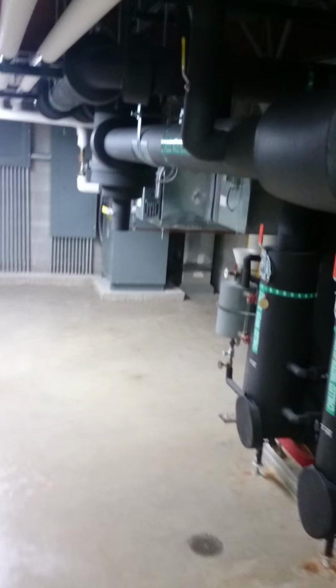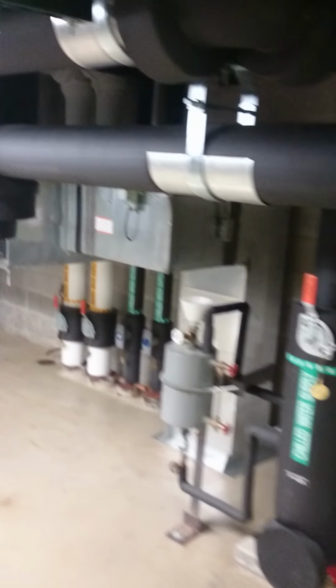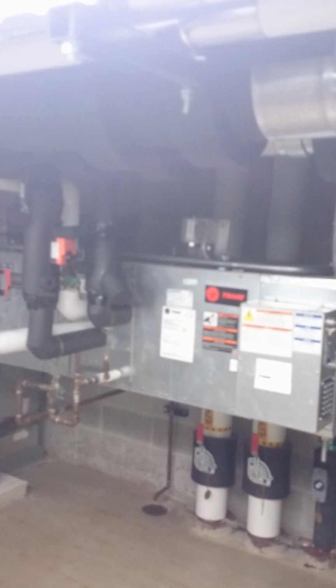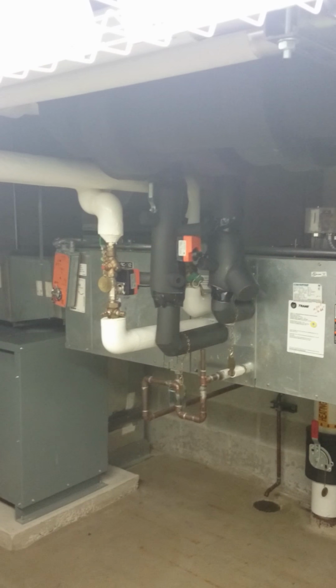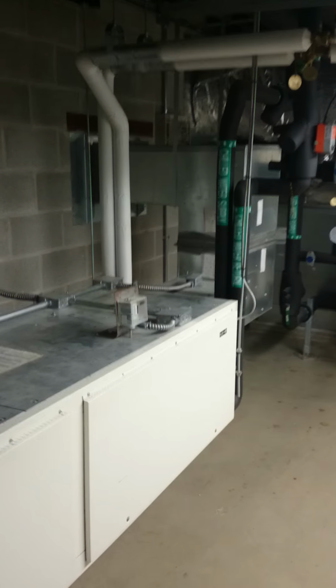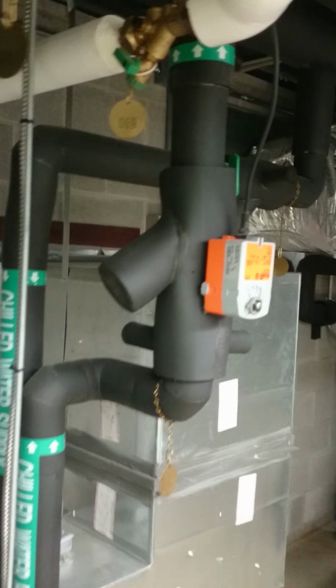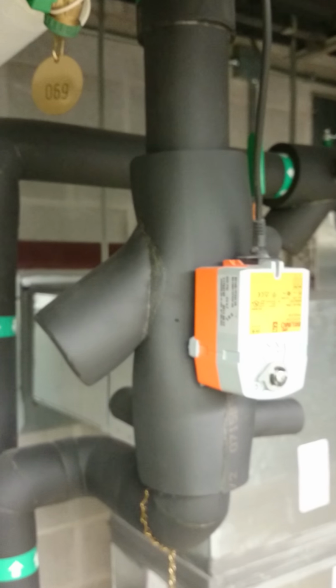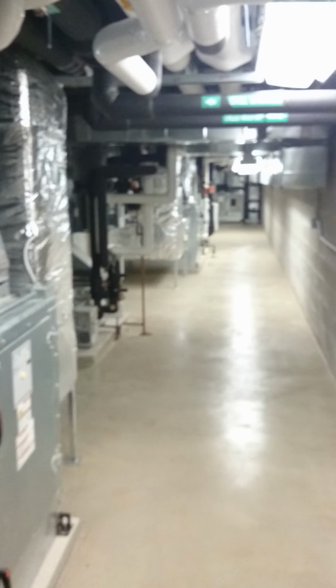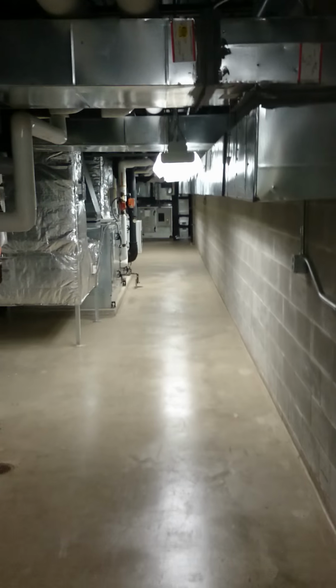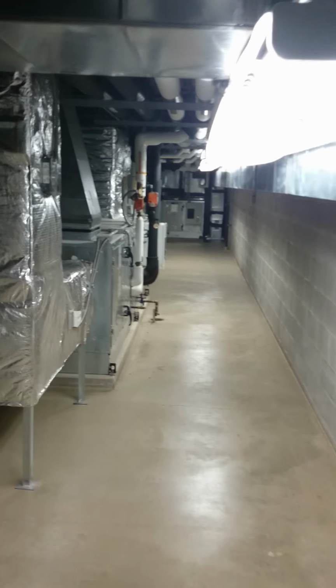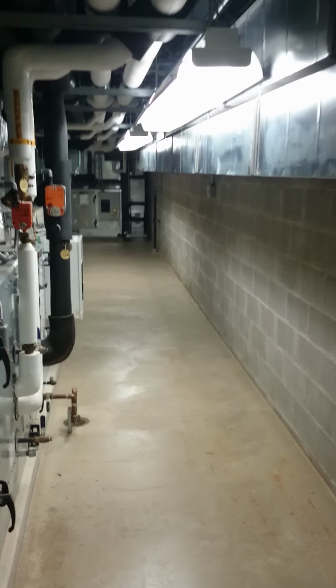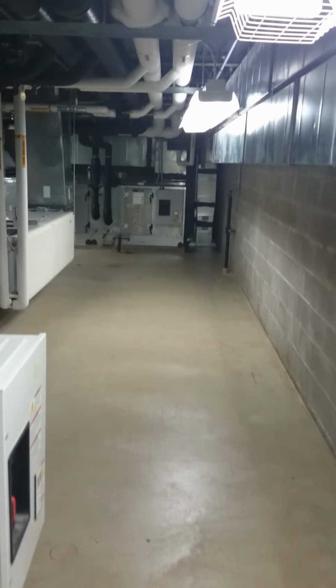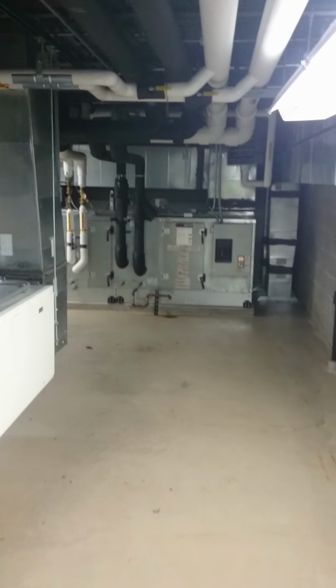So I figured we had to have some kind of flow problem, and being on a milder day, these are our air handlers that have chilled water coils and hot water coils in them. Being on a milder day, a lot of these coils weren't going to be calling for chilled water flow. So our actuators are shutting off. So I was wondering if we had maybe a lack of a bypass at the end of the loop, but somehow our flow was pretty much stopping. So we were deadheading our flow for some reason.